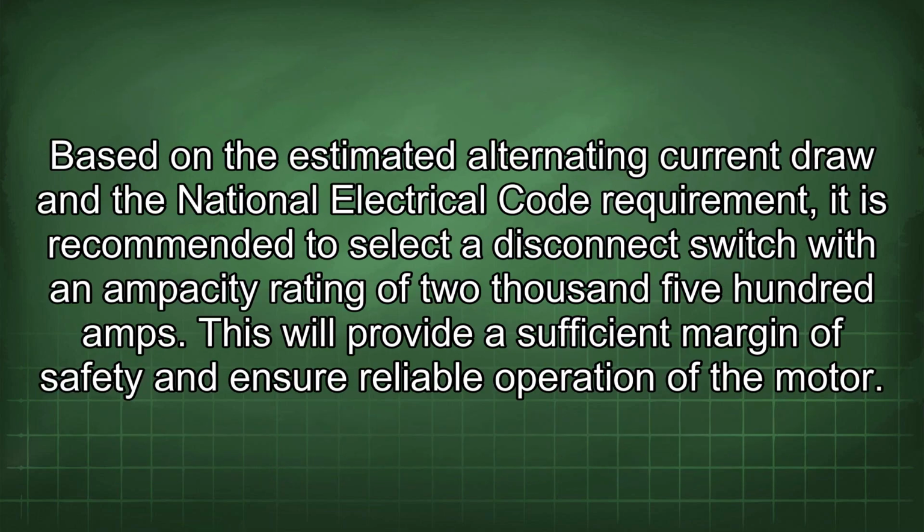Based on the estimated alternating current draw and the National Electrical Code requirement, it is recommended to select a disconnect switch with an ampacity rating of 2500 amps. This will provide a sufficient margin of safety and ensure reliable operation of the motor.